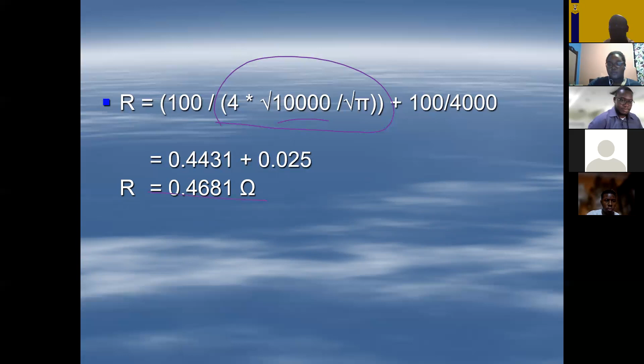Now, with that R, considering what the touch and step potential are based on the short circuit current that will be flowing - because that current, remember, we're diverting all of that to earth, that's the hope at least. So if we divert that to earth, it's going to flow through the earthing resistance, which is what we have calculated. So having calculated that, the potential rise, the ground potential rise, is 4,091.